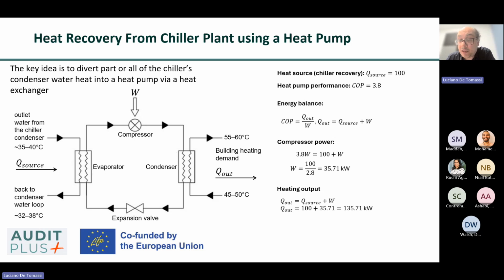The system is typically controlled so that heat recovery is prioritized when there is concurrent cooling and heating demand. When the heating demand is low, excess condenser heat is still rejected through the cooling tower or dry cooler to maintain system stability. When heating demand is high, more of the condenser heat is diverted through the heat pump, reducing or eliminating the need for boiler operation.